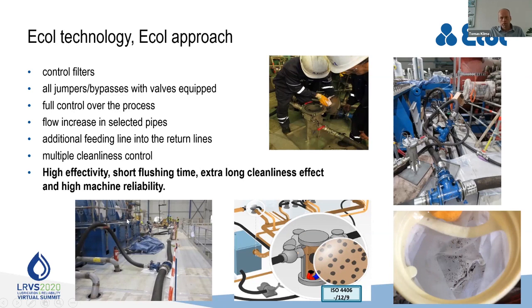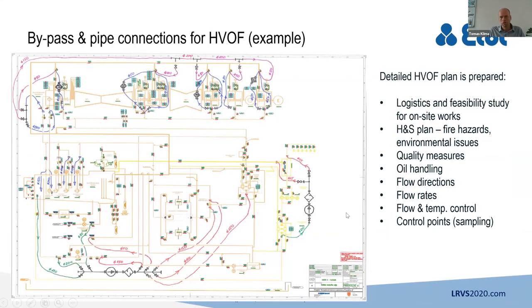High effectivity and short flushing time reached by such a flushing program, extra long cleanliness effect, and high machine reliability. Here you see the plan for flushing prepared by the engineering. Usually the planning which is prepared takes care of the quality measures of the oil handling, flow direction, and flow rates. The flow rates are controlled, and there are specified control points where we take the samples.